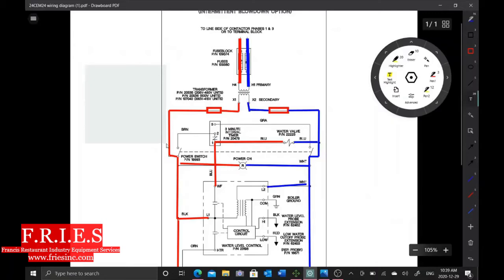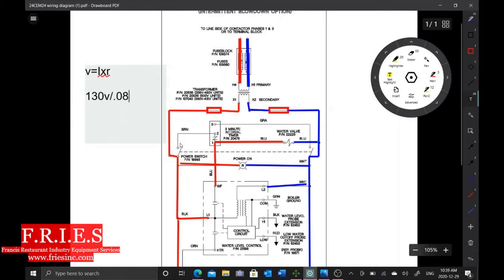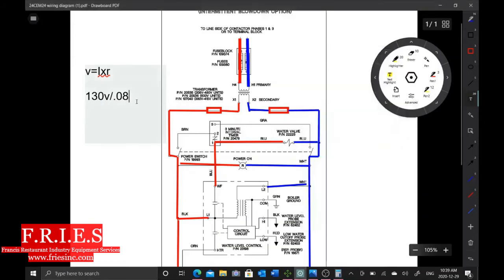All right, so I was getting 0.8 ohms. So if we just do our quick calculation here: voltage is equal to amperage times resistance. So our voltage is 130 volts, and if we divide that by 0.08 ohms, we get 162.5 amps.